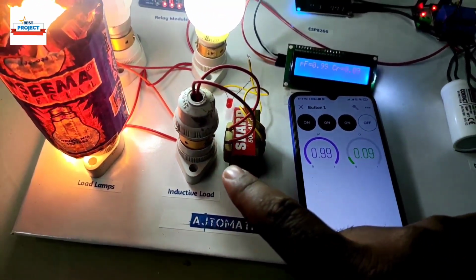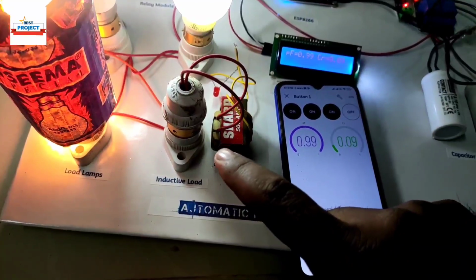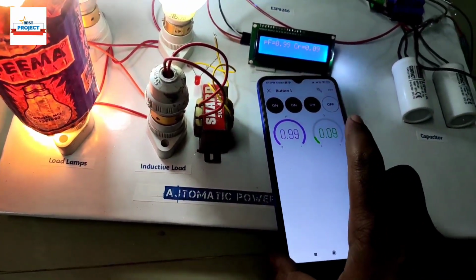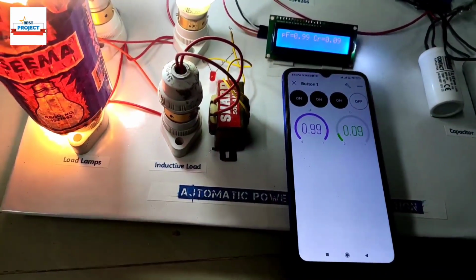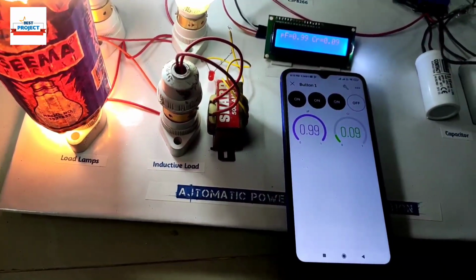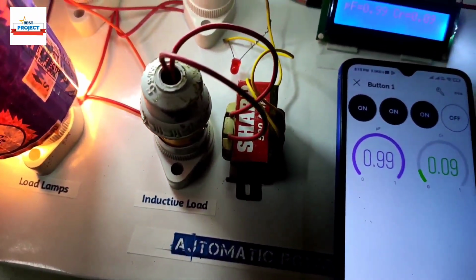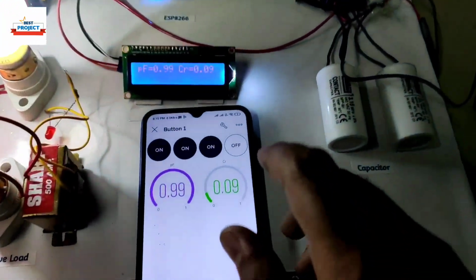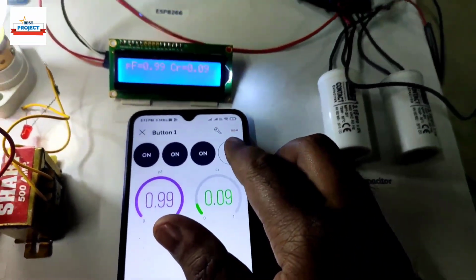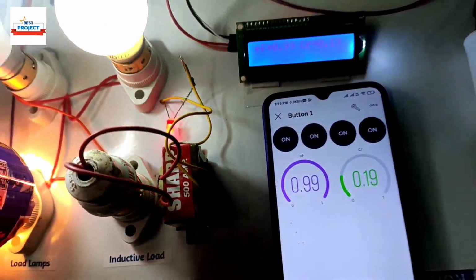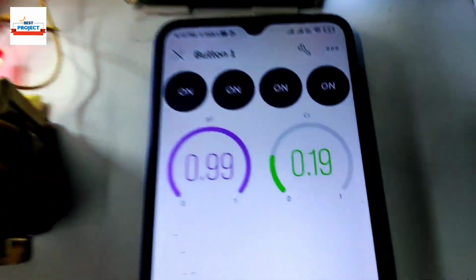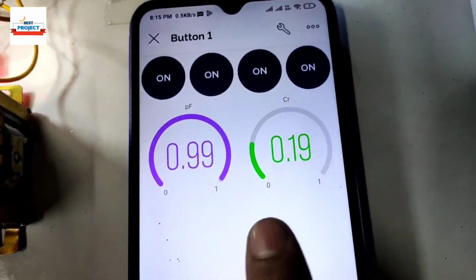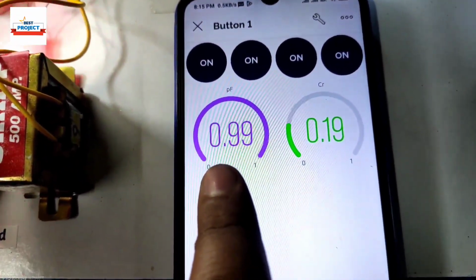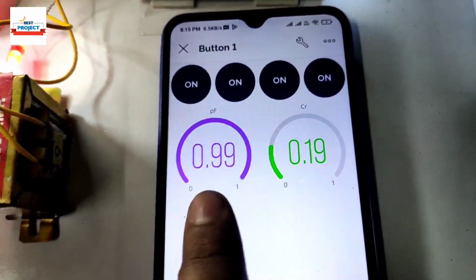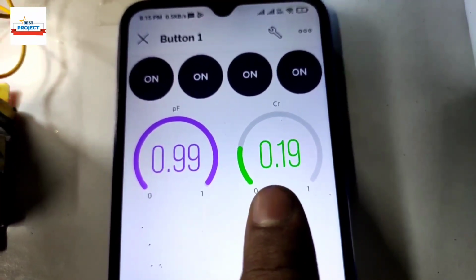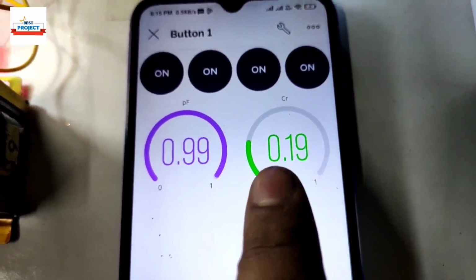Okay, as you know, an inductive load creates a lot of problems in power factor correction measurement, because the current lags the voltage angle more compared to a resistive load. So you can say the transformer is an inductive load, so I will turn on this load. See, the transformer is now on, and you can see the corrected value was 0.19, and the power factor is automatically corrected to 0.99.